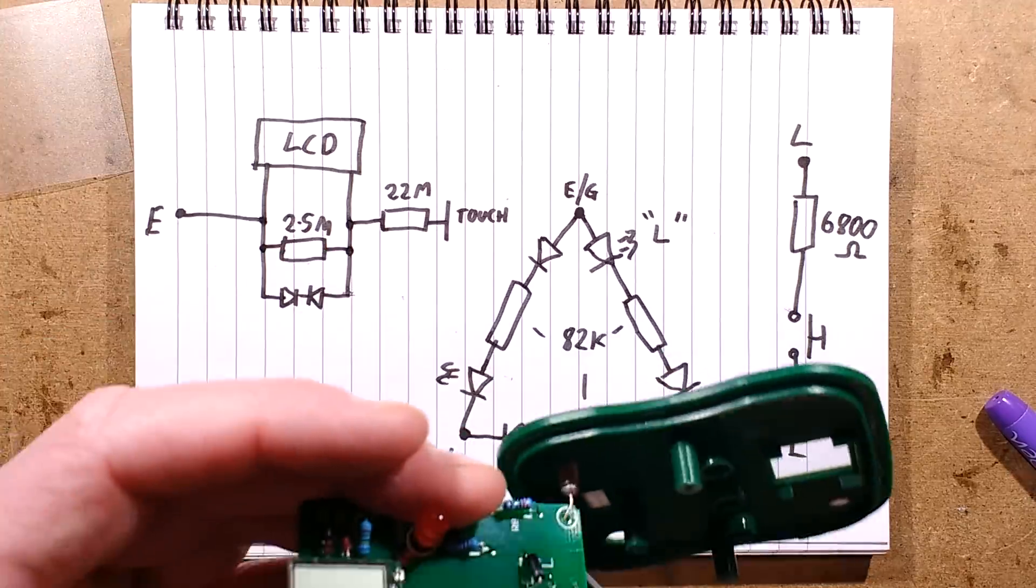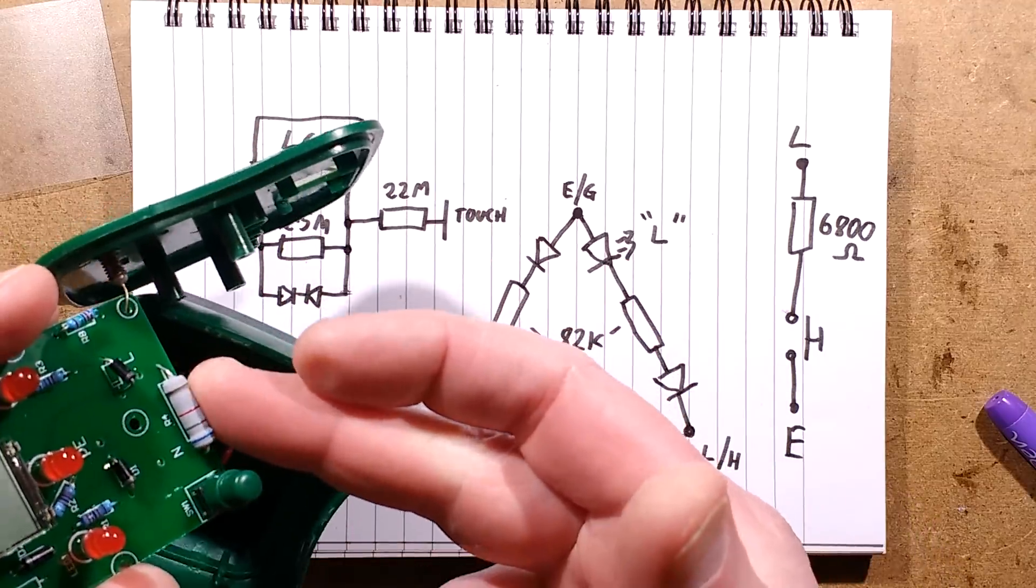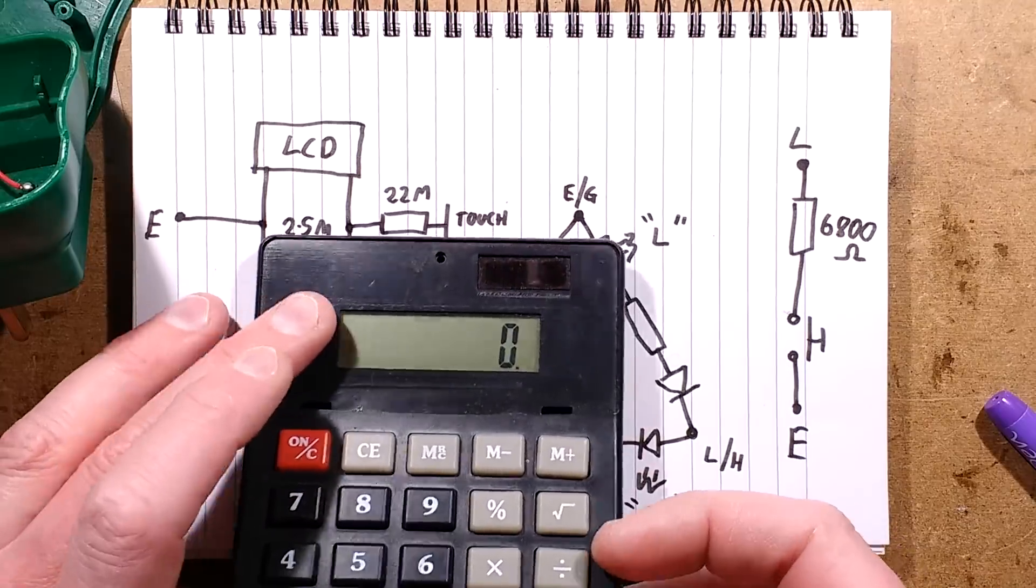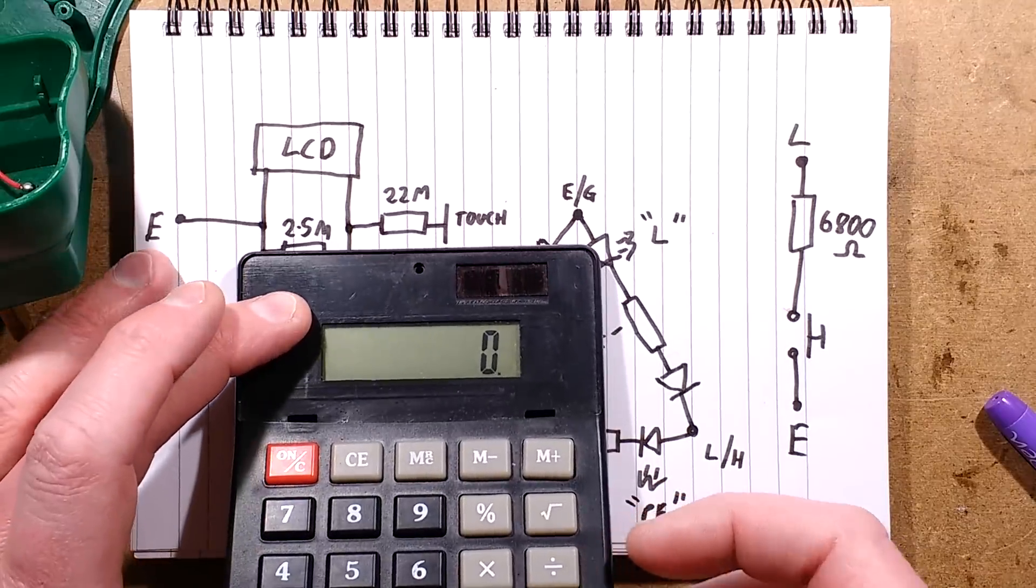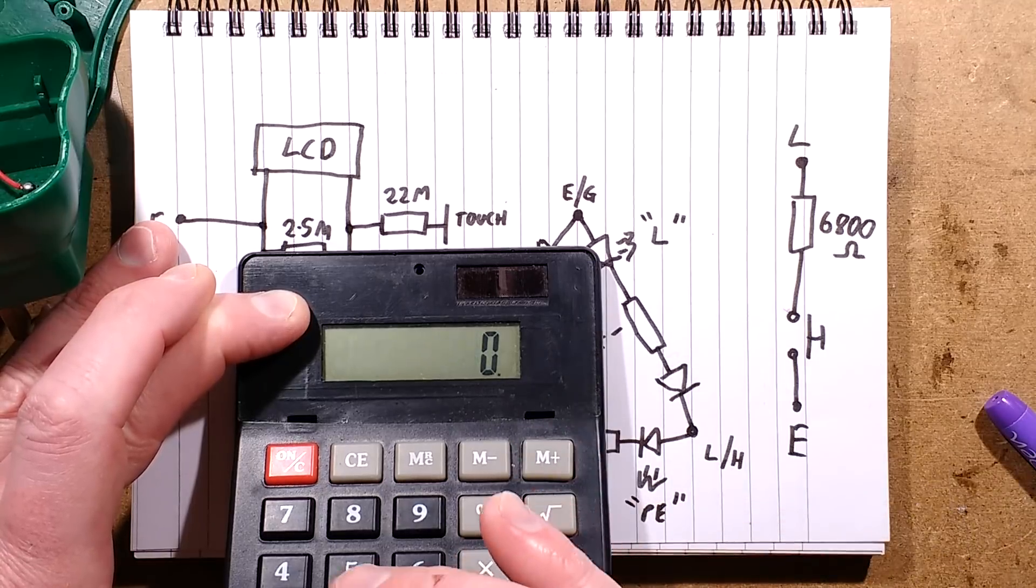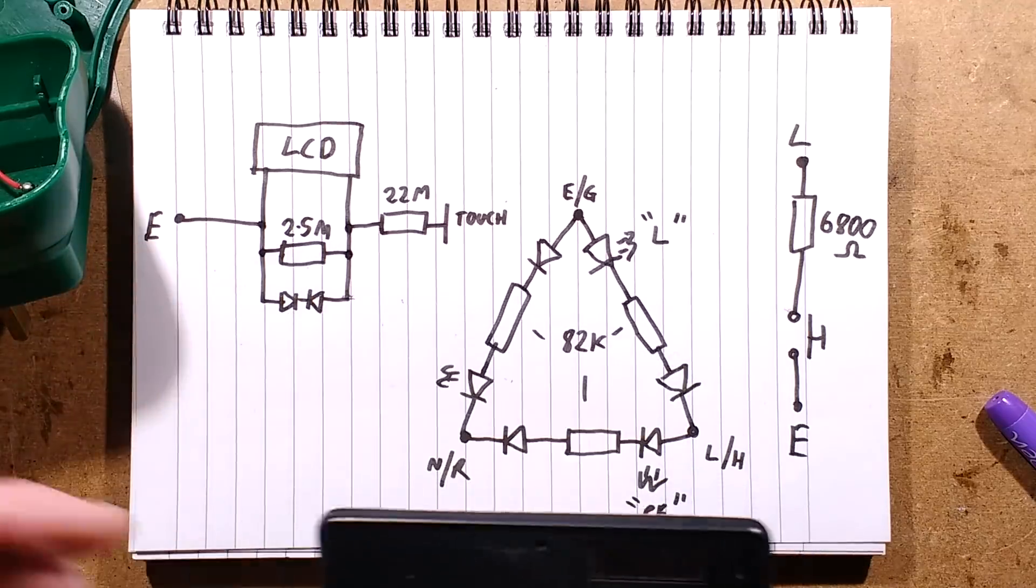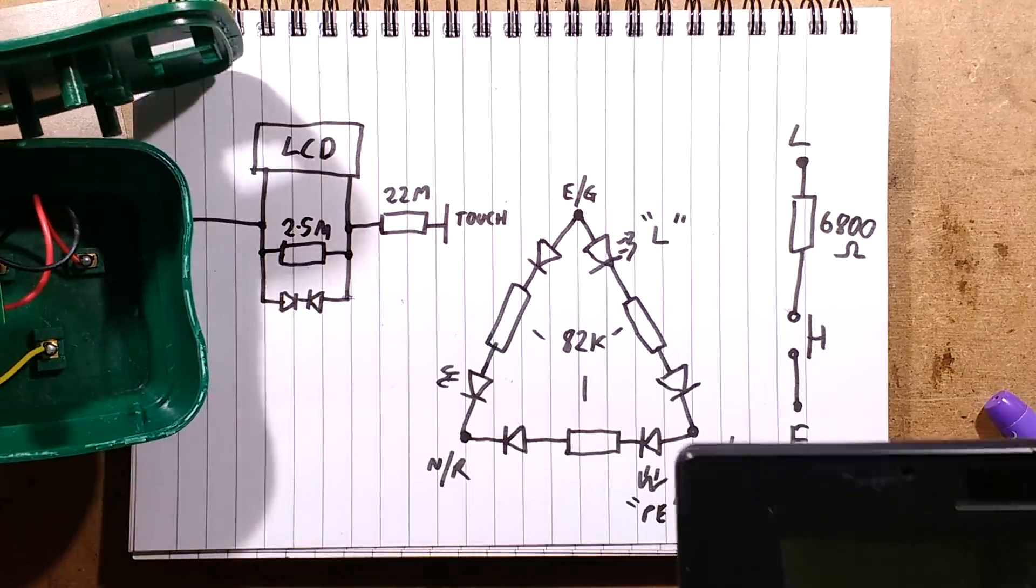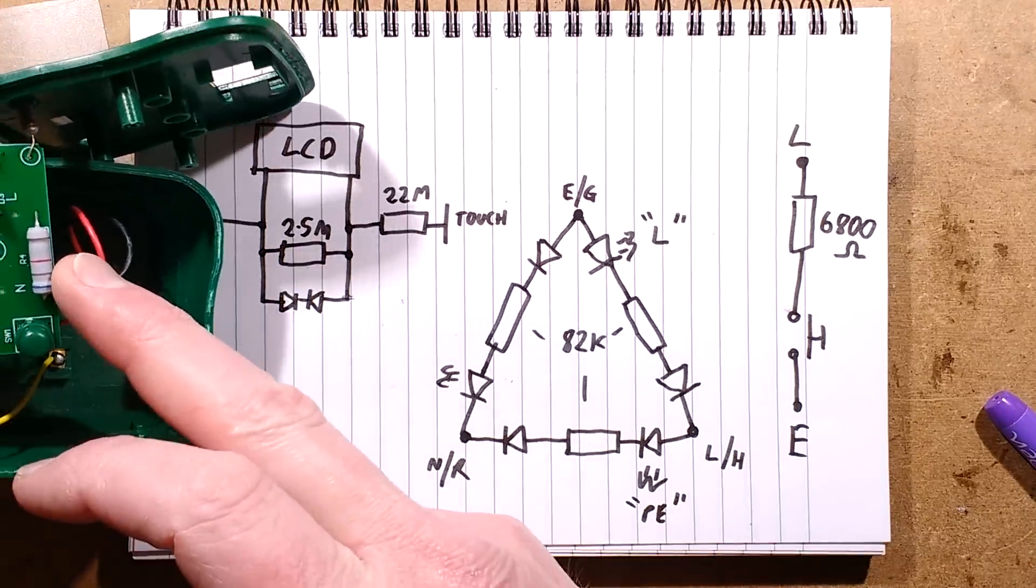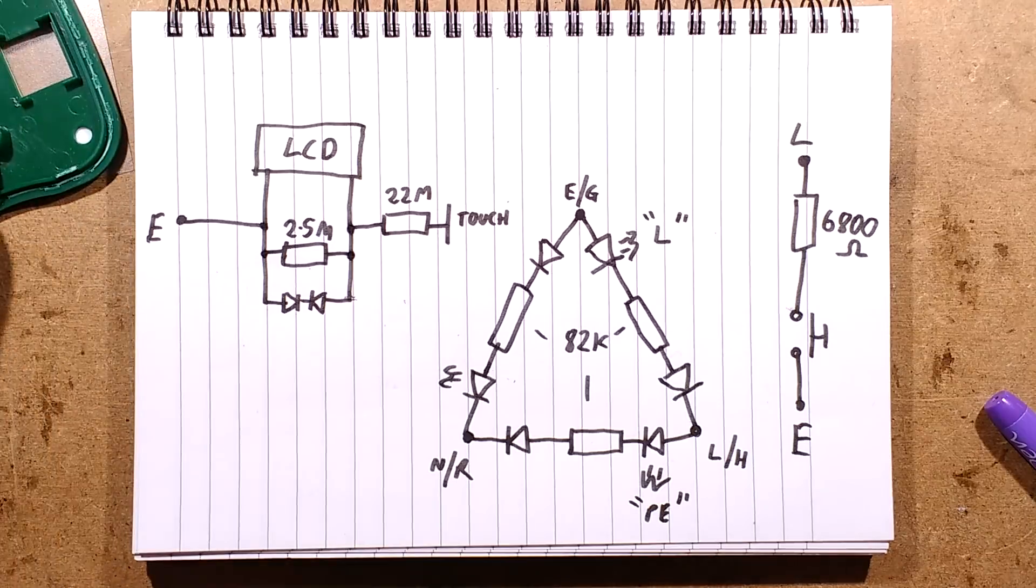It's notable: if it did not trip the tester, you can't keep that button held because if you do, that resistor is going to get very hot. How hot would it get? Typically, if that was 35 milliamps at 240 volts, P equals IV: 240 volts RMS times 0.035, it would get 8 watts hot. I think that looks like a 2 watt resistor. So it's okay for a brief spell at that power, but any longer and that's going to start getting very very hot and smoky and doing nasty things.